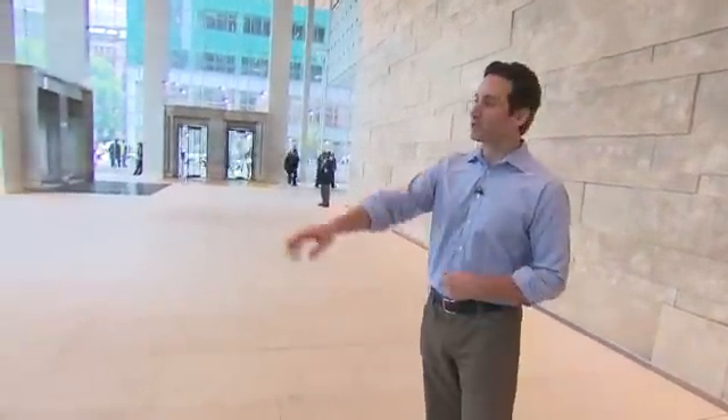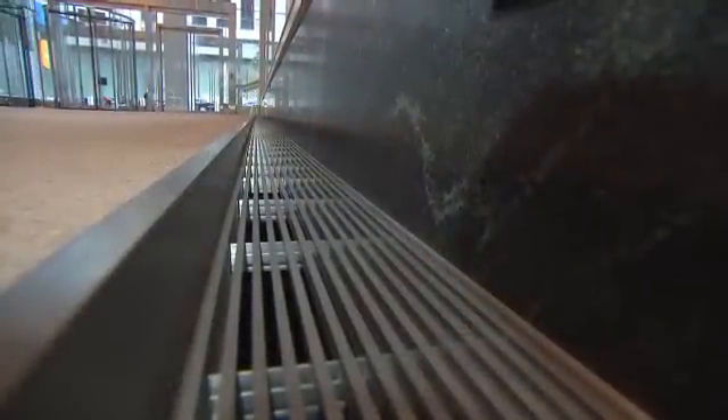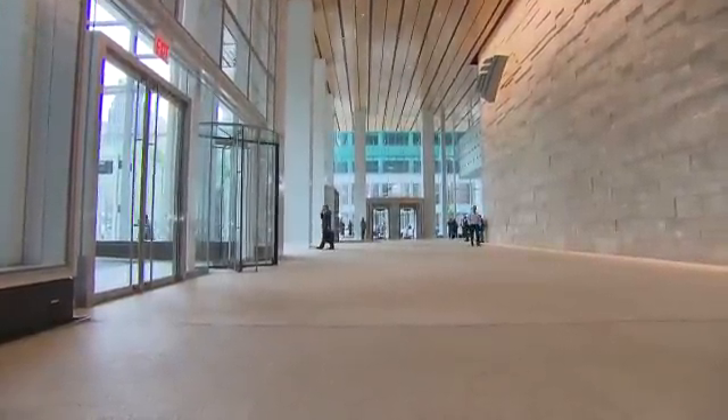The height of the space is quite tall — it's about a 38-foot tall volume of space, fairly large on the corner. What we were concerned about here was not heating and cooling the entire volume of the space. So the cooling is coming from underneath the floor. We have perimeter grills all along the outside wall here where the cold air is coming up, and also the floor underneath our feet has a radiant heating and cooling system in it.